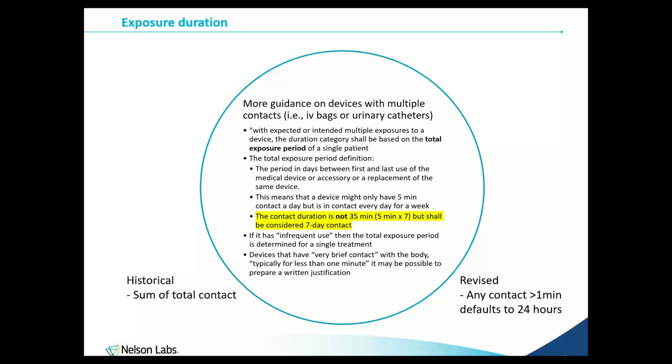And the reasoning behind that is even though the device might only have 5-minute contact, the chemistry being left behind in the vascular system is now being dealt with by the body throughout that day. And we don't know if it actually is metabolized and excreted, or if it starts to bioaccumulate over time.